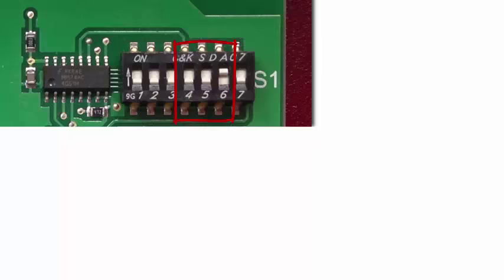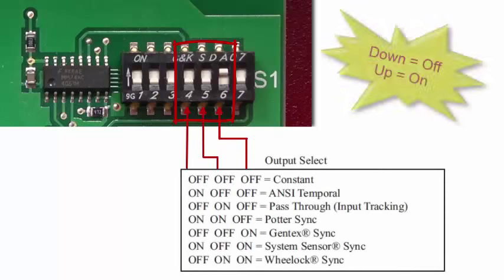The next 3 switches designate the output pattern for the notification circuit. Your option for each notification circuit is constant ON, ANSI temporal output, pass-through, POTR or AMSECO sync, Gentex sync, system sensor sync, and Wheelock sync.